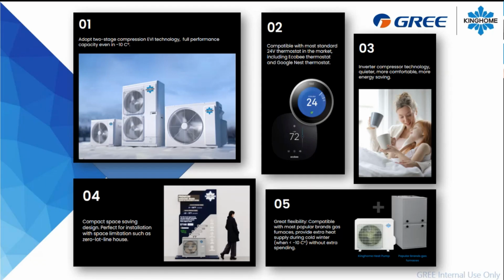So in that heat pump, you have a two-stage inverter compressor. And so it's really a good compressor, really reliable. It can operate at 100% of its capacity at minus 10 degrees Celsius. This unit is fully 24 volt compatible. So even through your thermostat to the outdoor unit, it will be a 24 volt connection. There's no communication line on this unit.